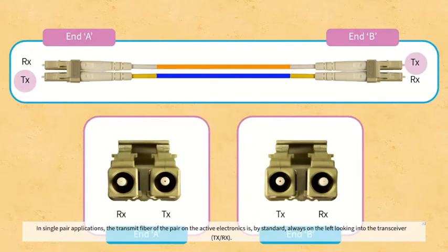In single pair applications, the transmit fiber of the pair on the active electronics is by standard always on the left looking into the transceiver transmit receive.